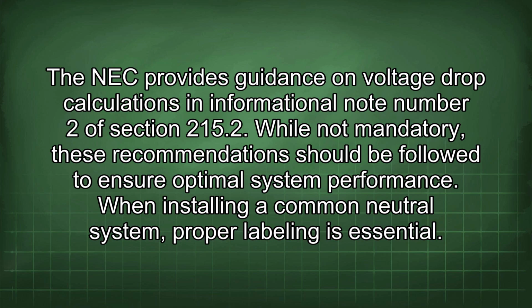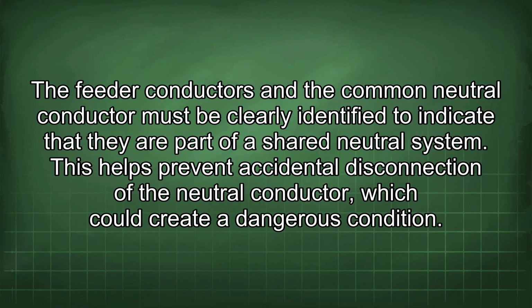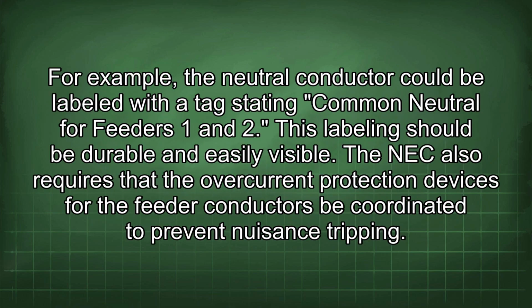When installing a common neutral system, proper labeling is essential. The feeder conductors and the common neutral conductor must be clearly identified to indicate that they are part of a shared neutral system. This helps prevent accidental disconnection of the neutral conductor, which could create a dangerous condition. For example, the neutral conductor could be labeled with a tag stating common neutral for feeders 1 and 2. This labeling should be durable and easily visible.